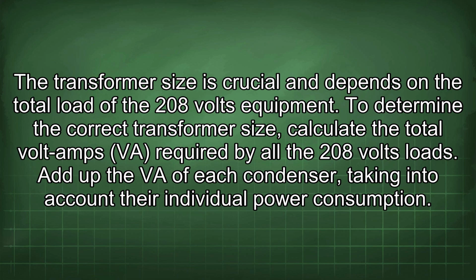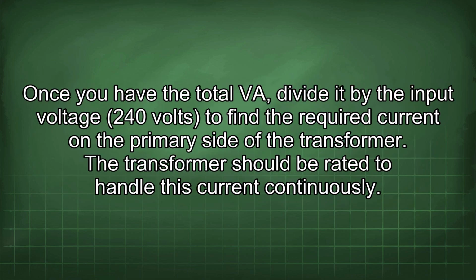To determine the correct transformer size, calculate the total volt-amps (VA) required by all the 208 volt loads. Add up the VA of each condenser, taking into account their individual power consumption. Once you have the total VA, divide it by the input voltage, 240 volts, to find the required current on the primary side of the transformer. The transformer should be rated to handle this current continuously.